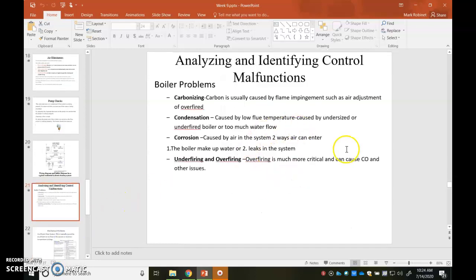Let's just take a look at analyzing and identifying control malfunctions. We're going to talk about boilers. They're very prone to carboning, which means that if the boiler burners aren't set up properly, they will create a lot of carbon and carbon monoxide. We'll talk in a couple minutes here about some TSSA mandates. I'll probably do it on a completely different video here. But what we're going to look at here is boiler problems.